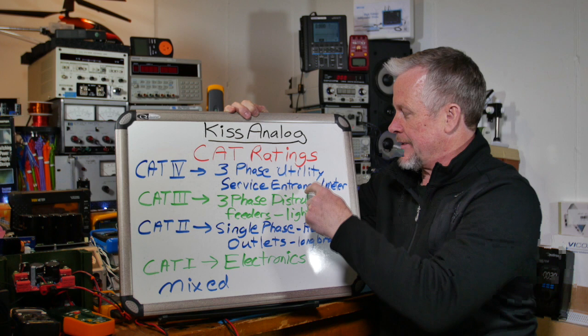And then some meters, like we saw earlier on the display, there are different features that different manufacturers have employed to try to help you stay safe. But all right, guys, I just wanted to go over that safety stuff with you, so if you see a review and you don't see the MOVs and all the stuff that you see on some other meters, well, those other meters might be category 4, and it's really hard. So if it's coming from a manufacturer that you even half trust, you've got to look into that yourself. I've got an insulation tester.